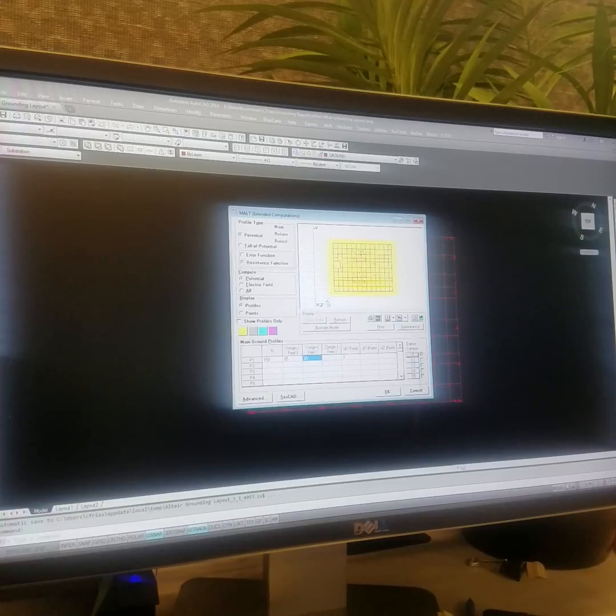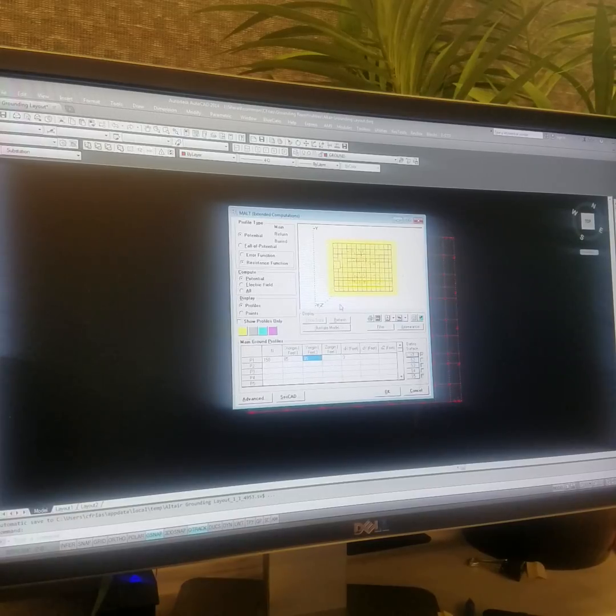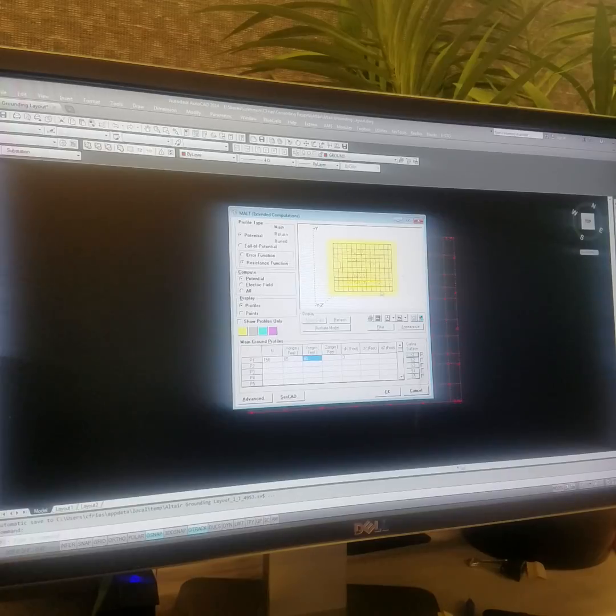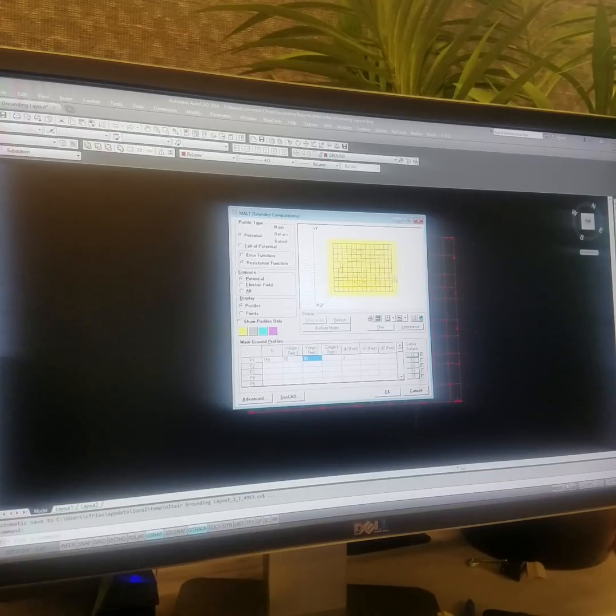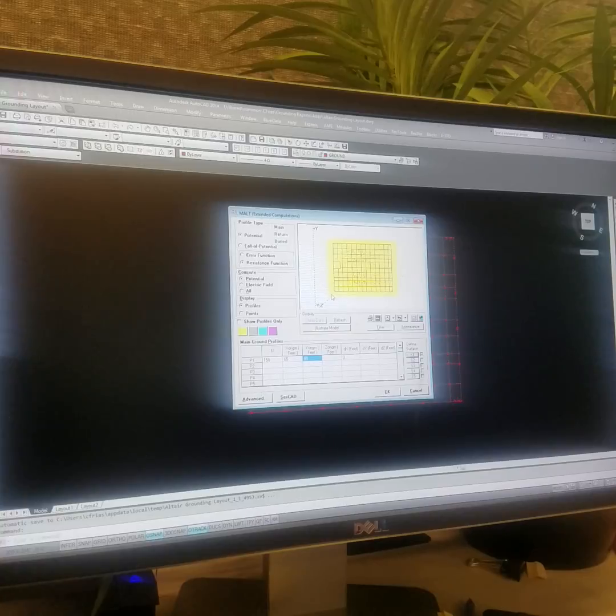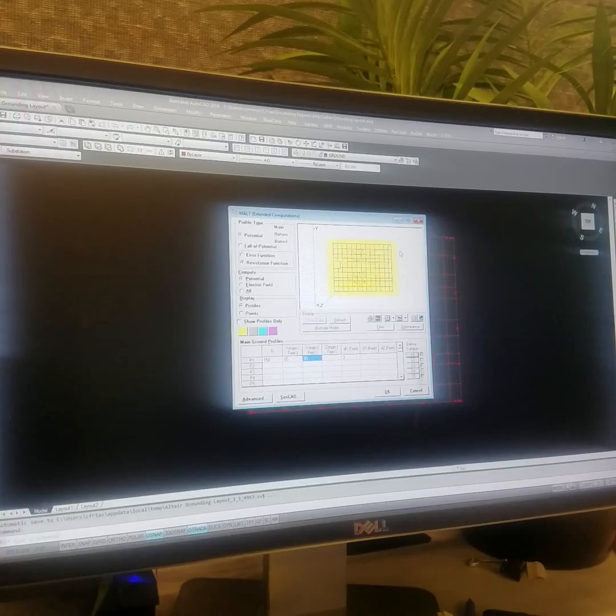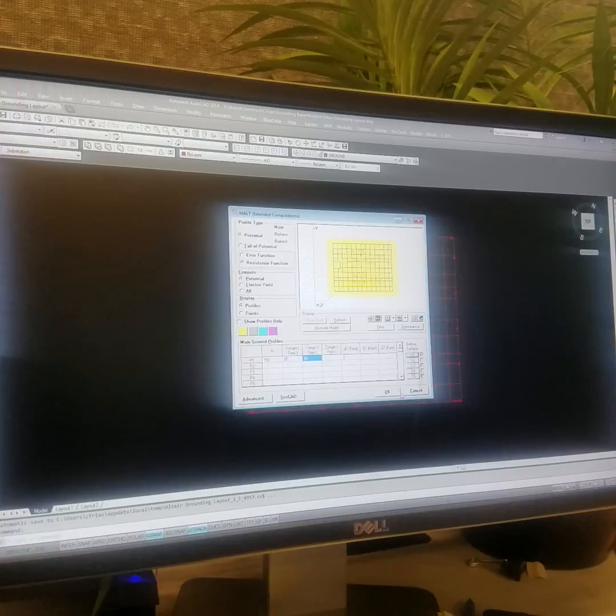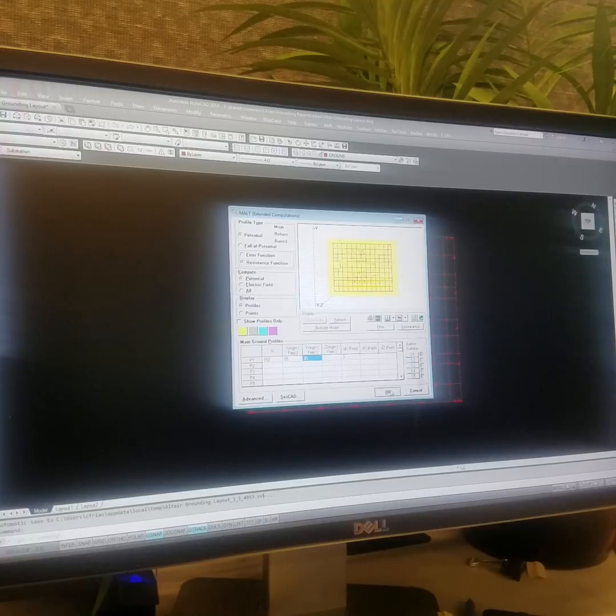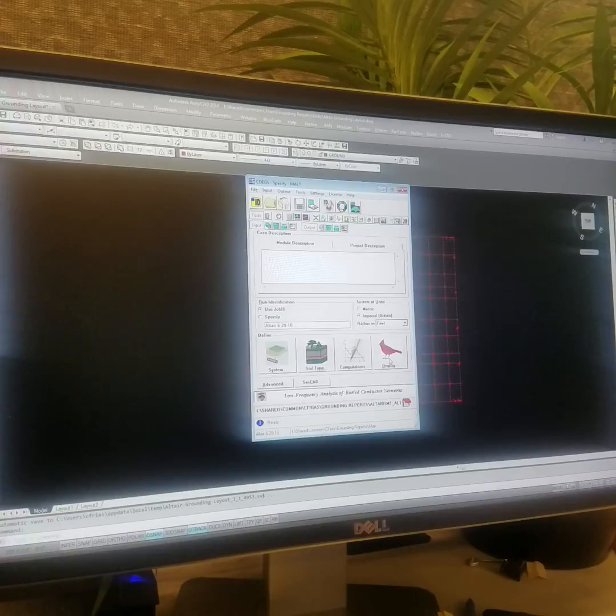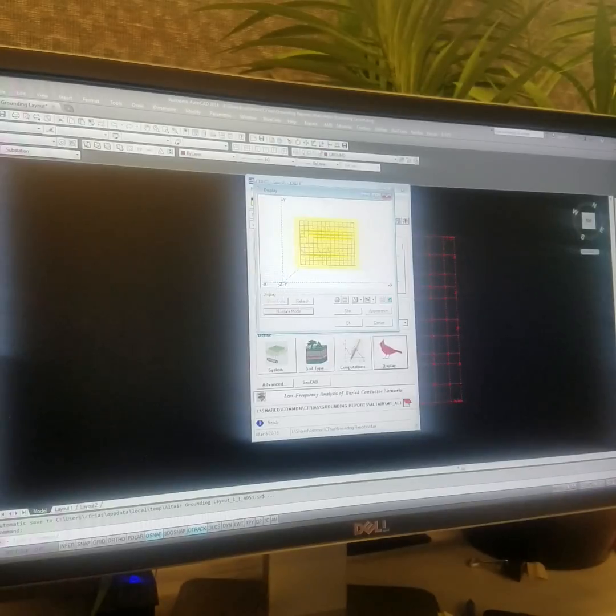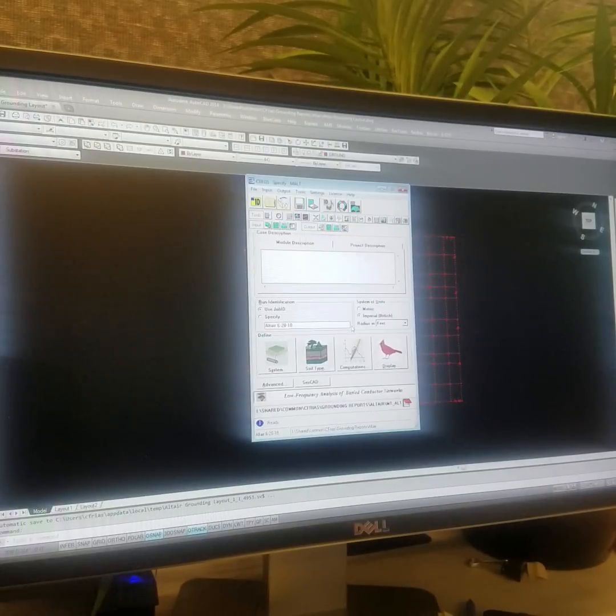So looks pretty good, right? That's a good general, you want to encapsulate some area around just to kind of give you, so there's probably a fence right here. And per our standards, we do have to protect three feet outside this fence, and it's also an IEEE requirement to protect the public. So you click okay. Look at everything if you want to look at it one more time, show your data what you're gonna process.